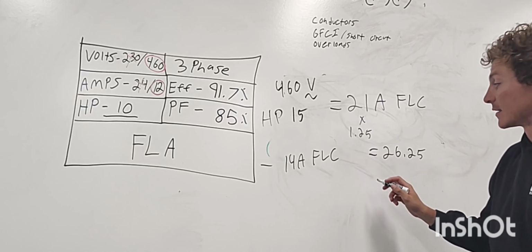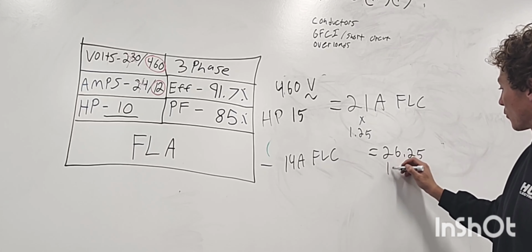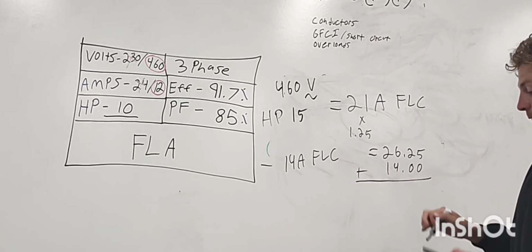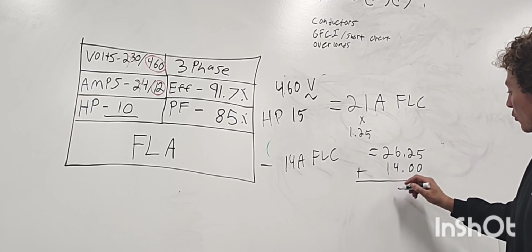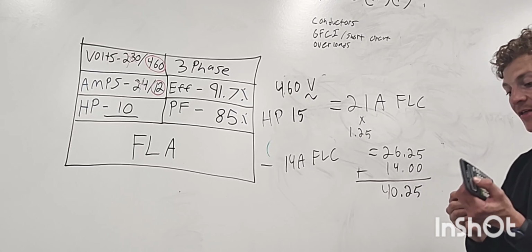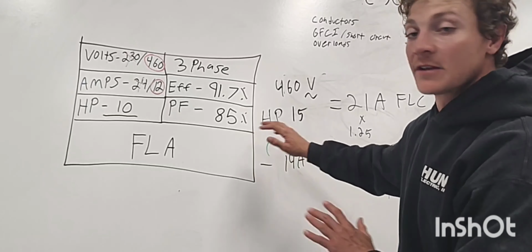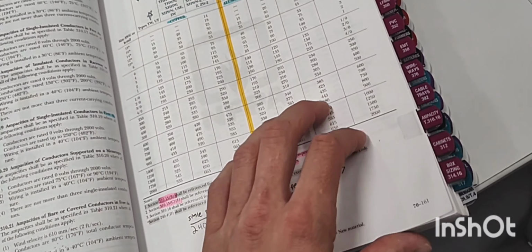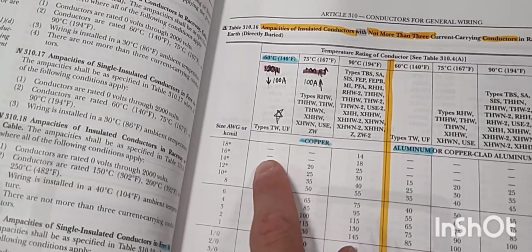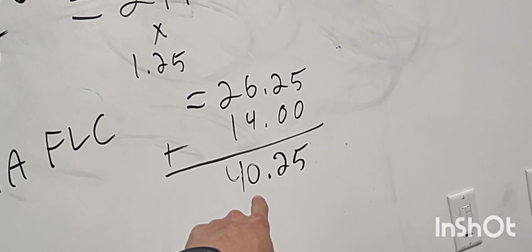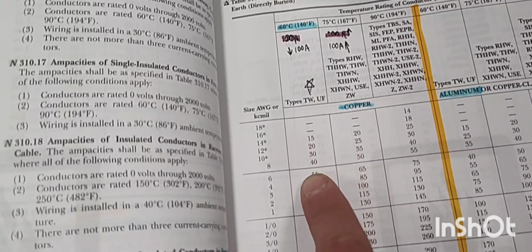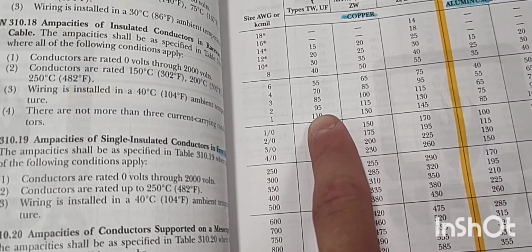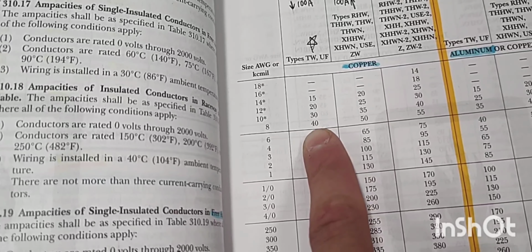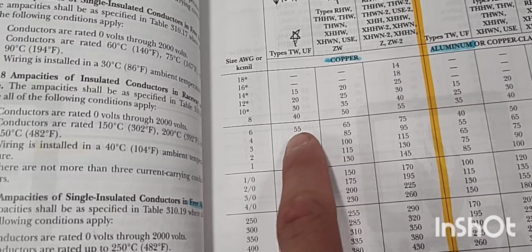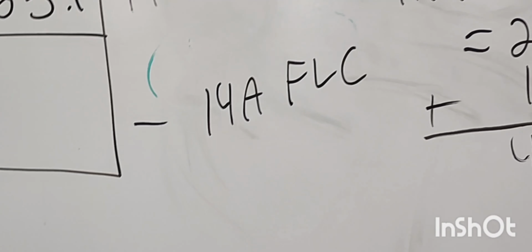26.25 plus the sum of the rest, 14 amps, 14.00, plus 40.25. And that is what we would size our conductors on if both of these were running off the same feeders. So let's come over here. Let's go into our ampacity tables. So we're still below 100 amps, 40.25, below 100 amps. Let's come down here to 40. Ooh, just hitting the cutoff, 40.25. We're going to have to size up. We're going to have to use 6 AWG for this one.